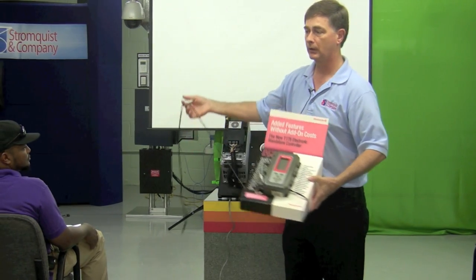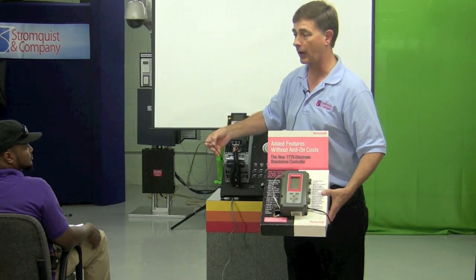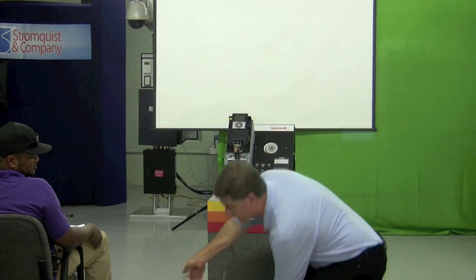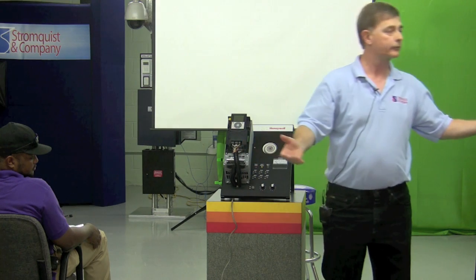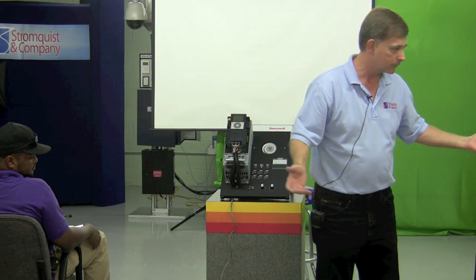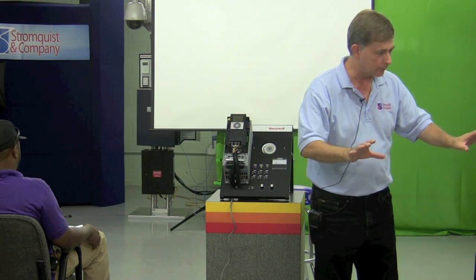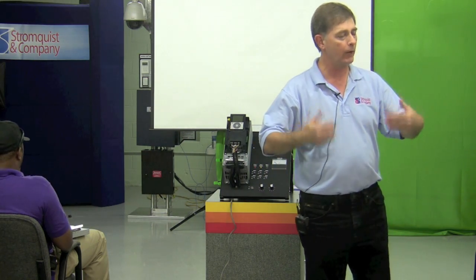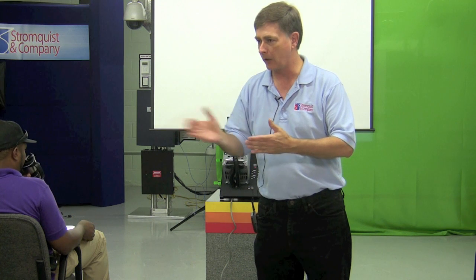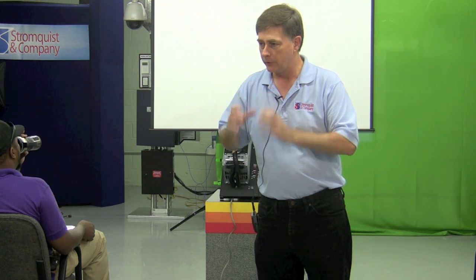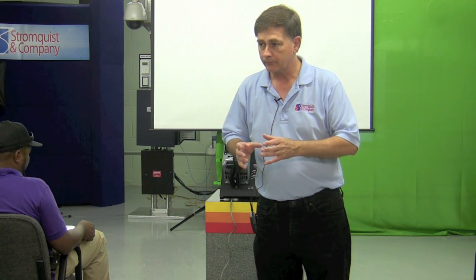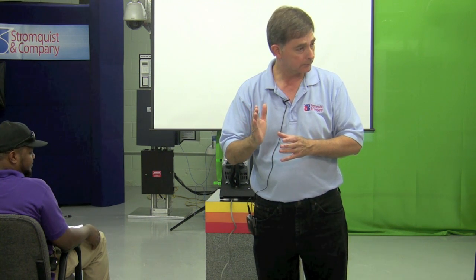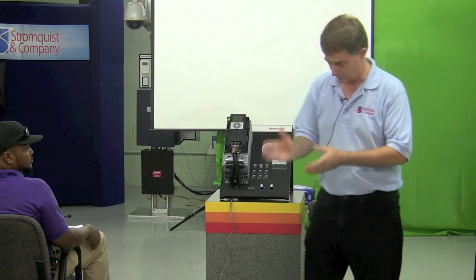We're using a variable frequency drive to control a cooling tower fan. What did we used to use to control our tower fans? Just a little aquastat. This is assuming you don't have a building automation system controlling it — if you have a standalone setup, just an aquastat. With a VFD you can throttle the frequency back and save a lot of money on your tower fans.